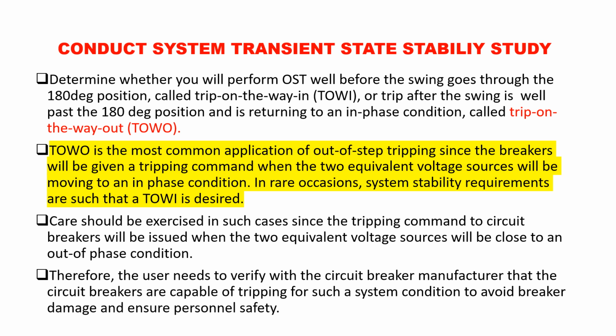So we also determine the point at which the systems are going close to 180 degrees away from each other, and you can have a tripping at this point, when the generator is going through the 180-degree out of phase position, and that is known as the trip on the way in.